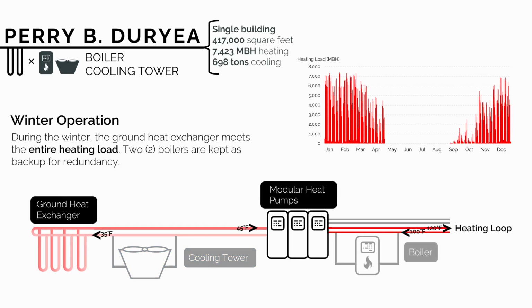Important to note, when we downsized the bore field, we're still able to handle all of the heating load with the ground heat exchanger. So you can see the temperatures there are quite low. That's kind of the extreme case where we've refurbed all the air handling units in the building. They're going to be able to accept the lower temperature heating water. So the heat pumps, in conjunction with the ground heat exchanger, are going to be able to provide all the heating for the building.